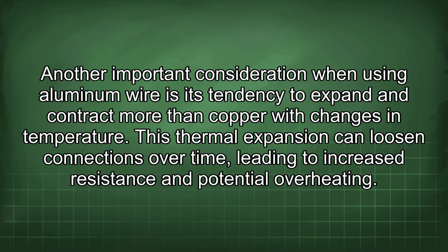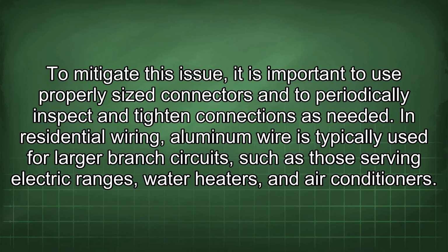Another important consideration when using aluminum wire is its tendency to expand and contract more than copper with changes in temperature. This thermal expansion can loosen connections over time, leading to increased resistance and potential overheating. To mitigate this issue, it is important to use properly sized connectors and to periodically inspect and tighten connections as needed.